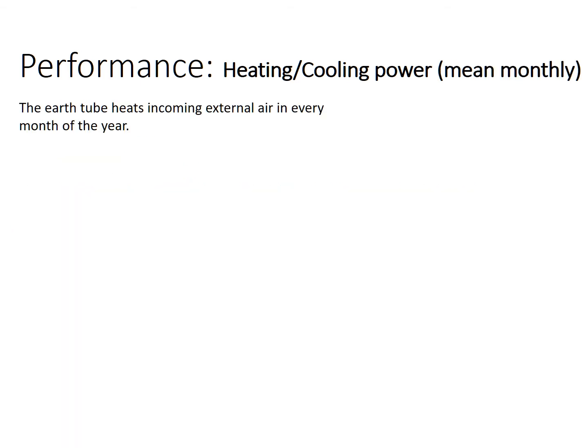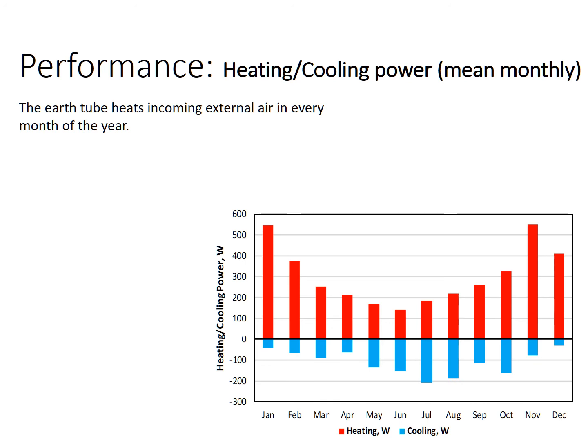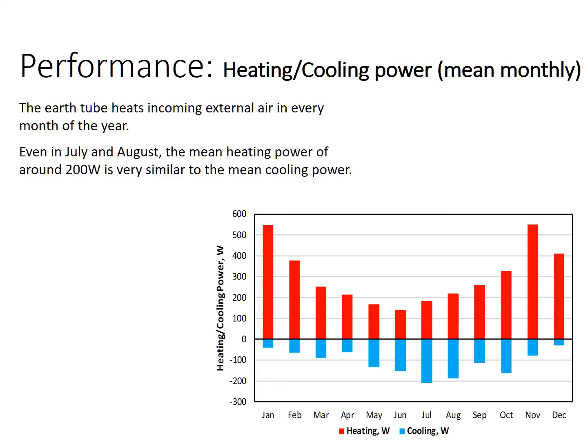In looking at monthly data, the earth tube heats incoming external air in every month of the year, even in the summer. We can see here, this is January to December. These are average results for each month over the 6 years. So as heating in the summer is more or less the same power as the cooling in the summer, very similar, which probably reflects cool mornings or cool nighttime air.